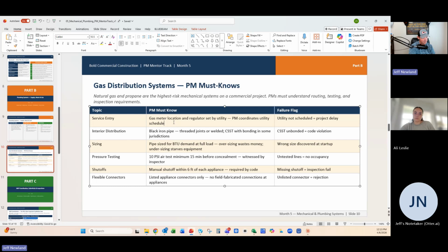Gas is measured in BTUs, so you can take your HVAC schedule, your plumbing schedule, and see what exactly is being run by gas, if anything, and it should tell you how many BTUs that's pulling. Then you can tell the energy company that we're going to have this much, and we need this amount of pressure for the gas meter. That's the most important thing to remember.